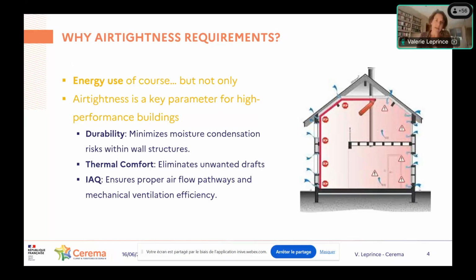The thing is that airtightness is a key parameter for high-performance buildings for their durability because it minimizes moisture condensation risk within the wall structure. It's also very important for thermal comfort because it eliminates unwanted drafts along the building. And for us, it's also very important for indoor air quality because in France, ventilation systems rely almost only on extract-only systems, with extraction in the bathroom and kitchen, and with natural air inlets located in the bedrooms and the living room.